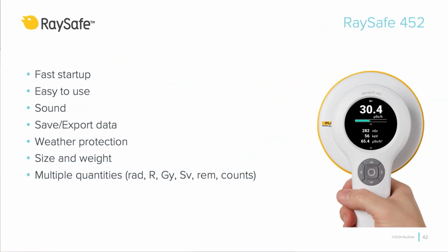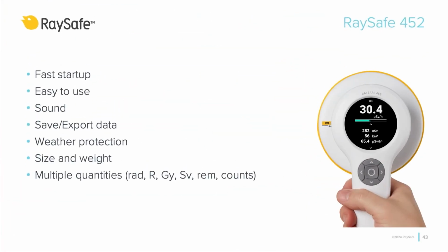Other features we have managed to create are fast startup. Most ion chambers, for example, will need to be idle for a couple of minutes after startup before being used. RaySafe 452 is ready directly after startup. It has an intuitive and easily understood interface with just a few settings. You can turn on or off sound or set alarm levels.